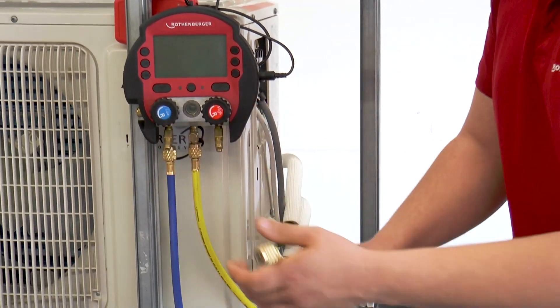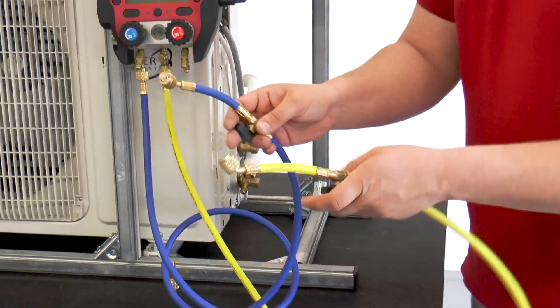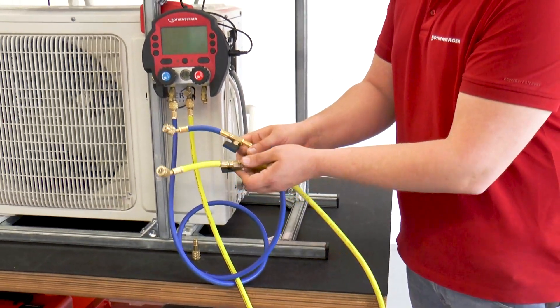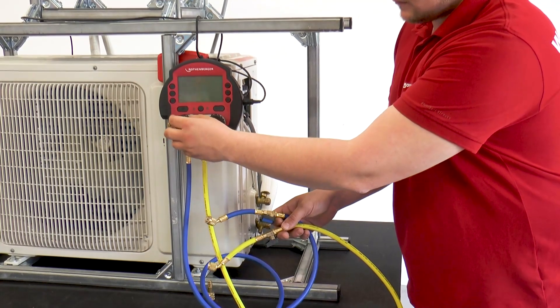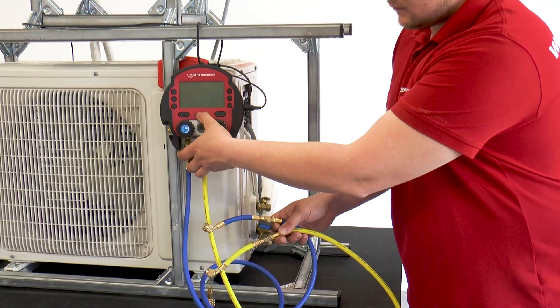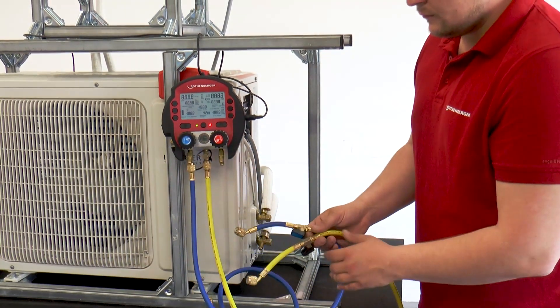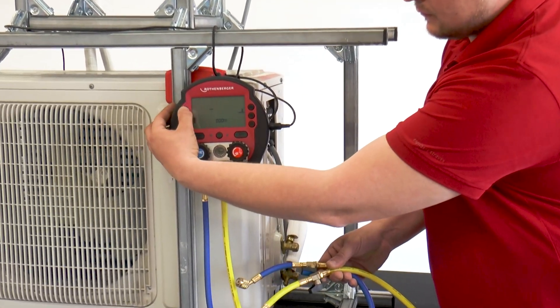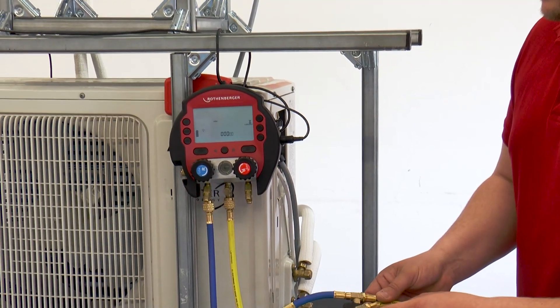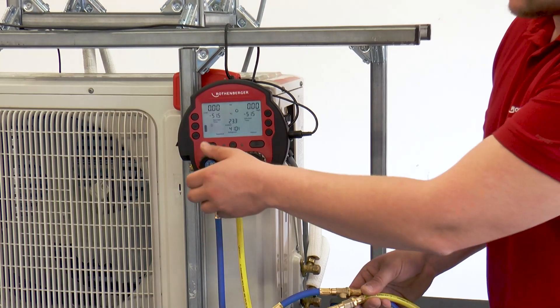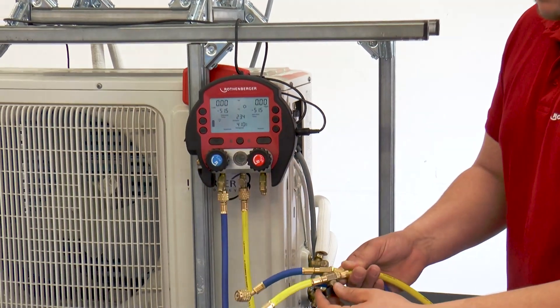After the hoses have been connected to the ROCOOL 600, with the shut-off valves of the hoses open, the valves of the ROCOOL are opened and the unit is switched on. Now, the ROCOOL 600 calibrates itself to the ambient air pressure. As soon as the ROCOOL has calibrated itself, the working valves are closed.